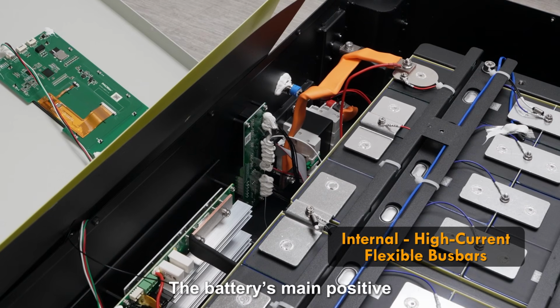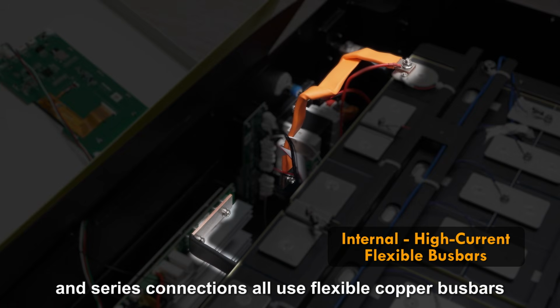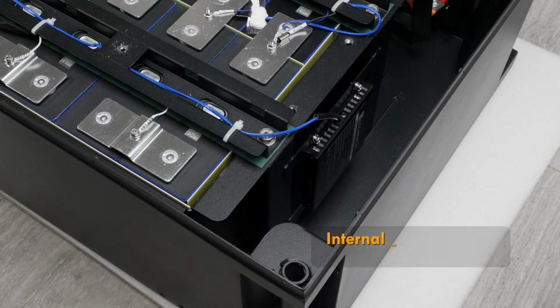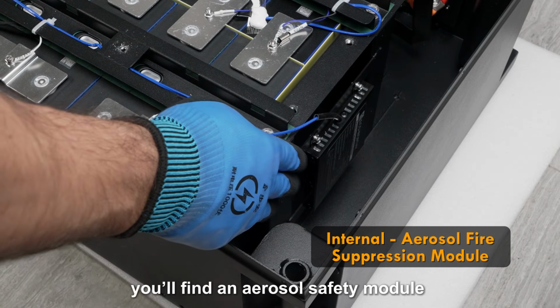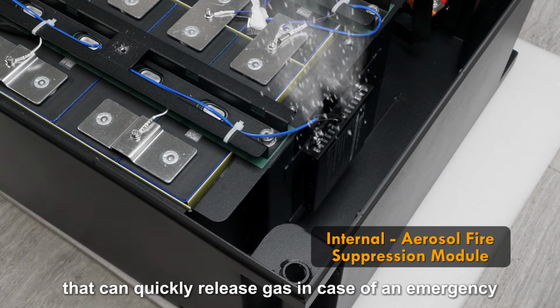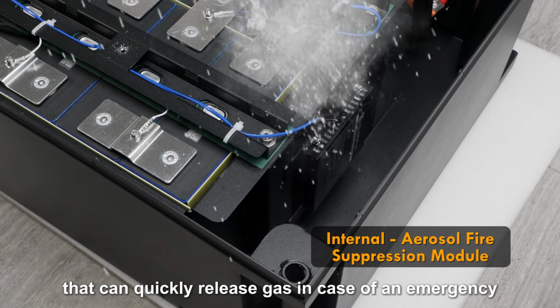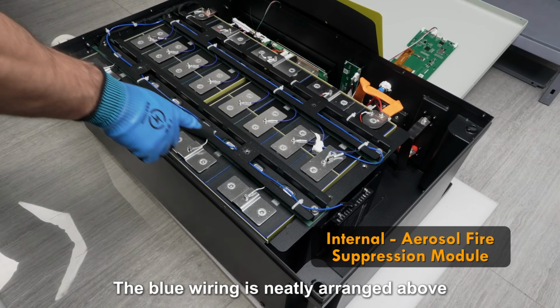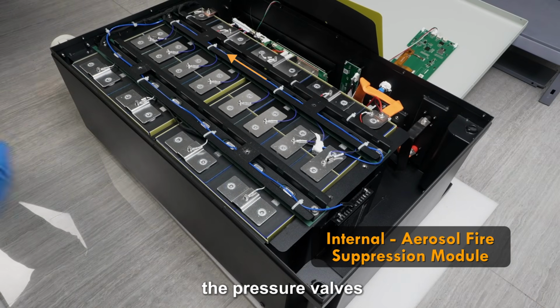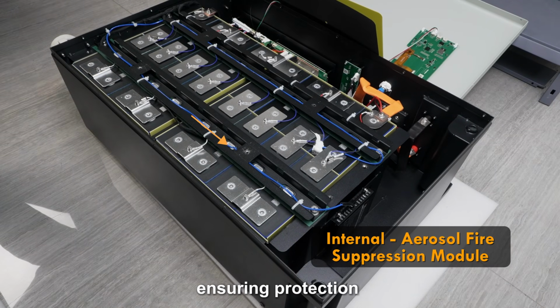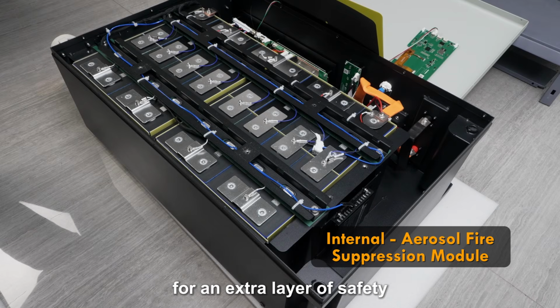The battery's main positive, main negative and series connections all use flexible copper bus bars. Compared to silicone wires, these bus bars handle higher current, provide more reliable connections and take up less space. On top of the cells, you'll find an aerosol safety module that can quickly release gas in case of an emergency. The blue wiring is neatly arranged above the pressure valves, ensuring protection is triggered immediately for an extra layer of safety.